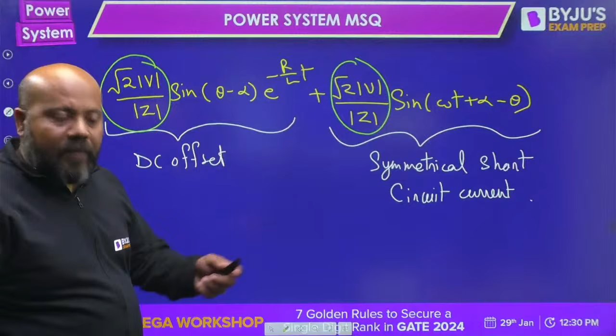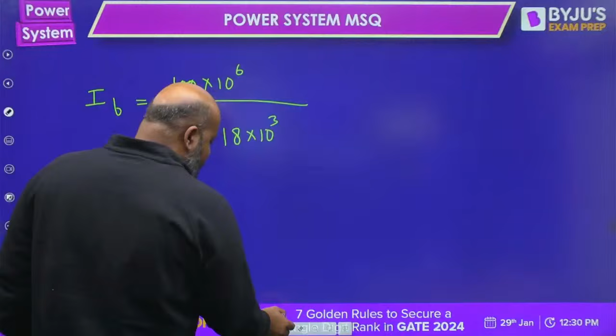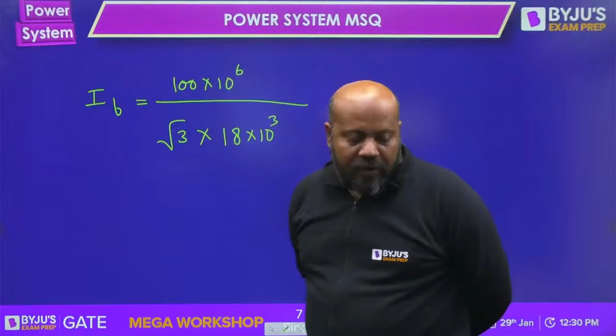Now, what is this symmetrical short circuit current? Let me write the base current value here. What is going to be the base current? Because everything we are getting in per unit, so base current you have to find from this 100 MVA, root 3, and the voltage, which is 18 kilovolt. No need of power factor because it is MVA only. Just find this value - what is the value you are getting for the base current? It is 3207.5 amperes. Please cross check this value as per my reference.